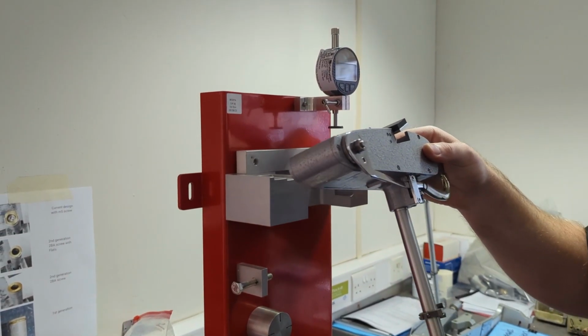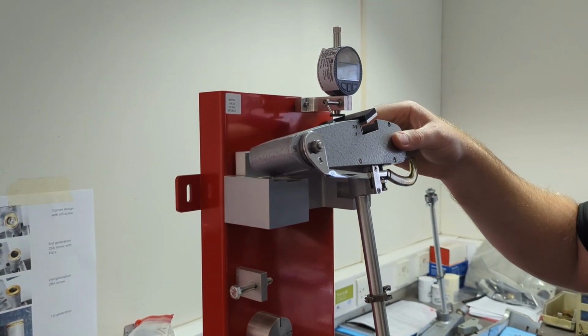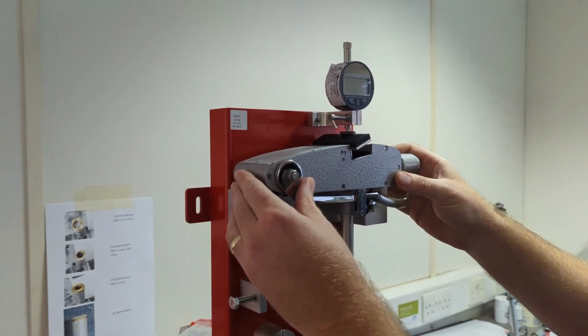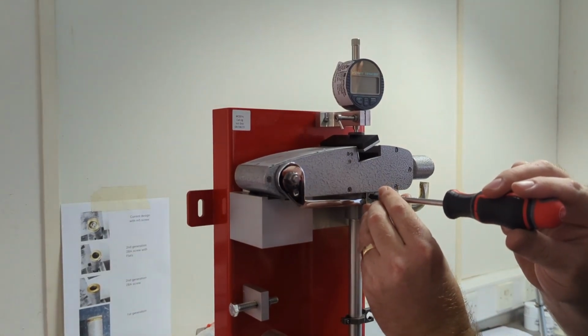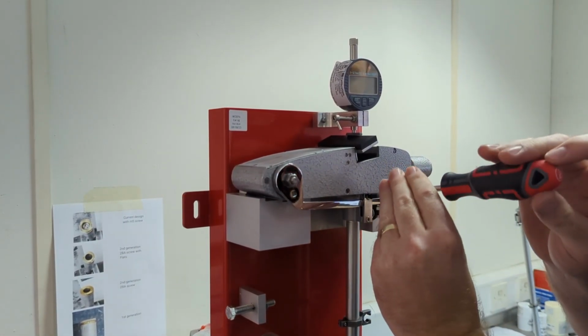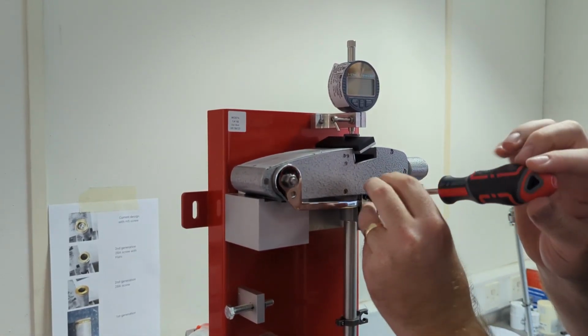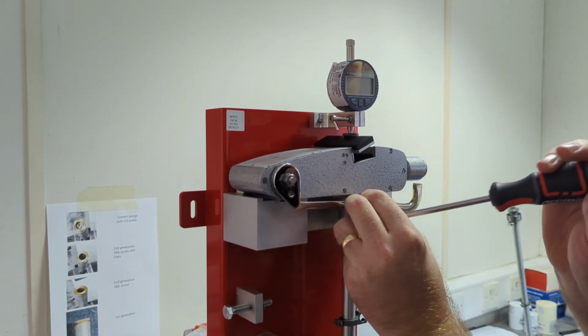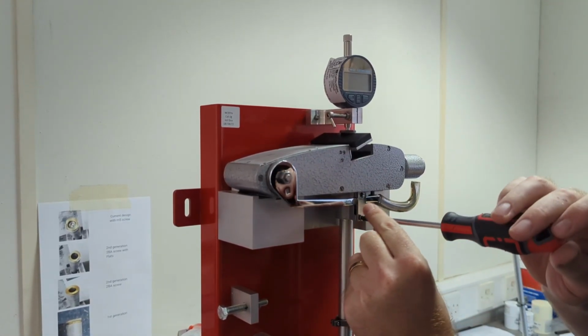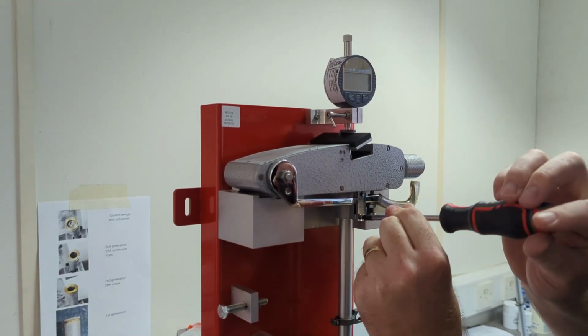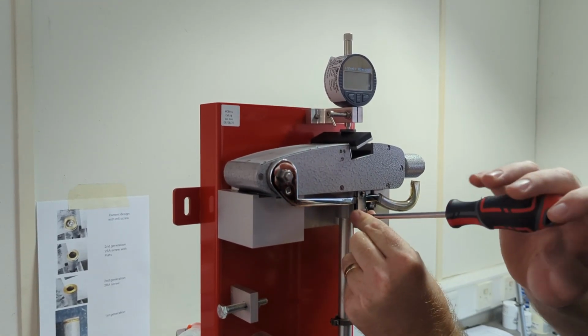Now we're going to set the spring tension at 4.5mm deflection using the jig. First you'll want to mount the foot upside down on the top shelf of the jig. There are recesses in the jig to allow secure placement. Then you can remove the screws and cover plate to expose the mounting point on the slider lift arm.